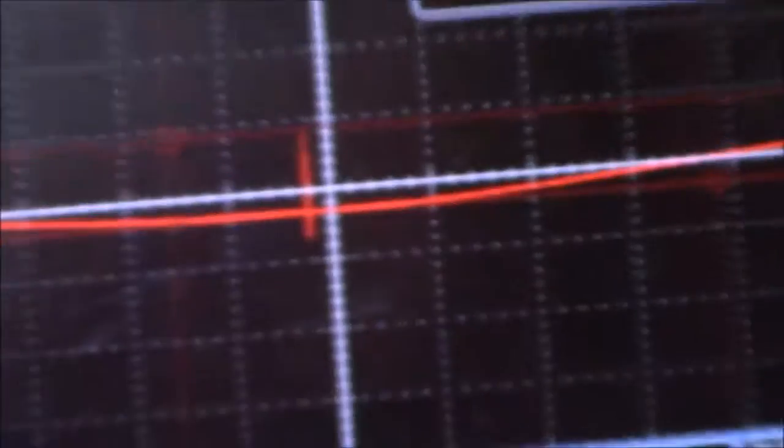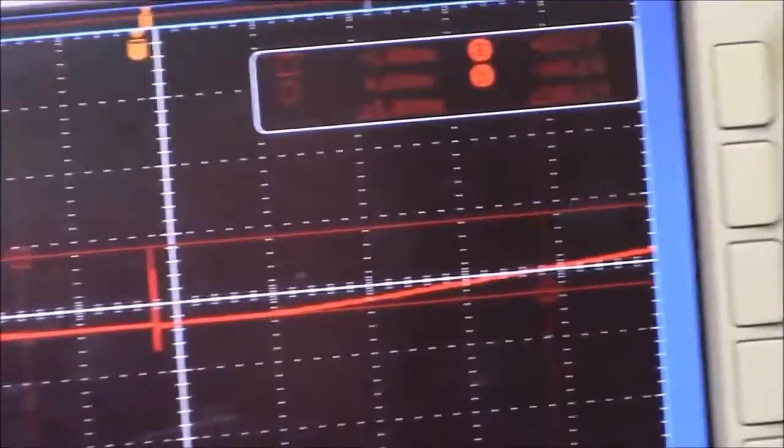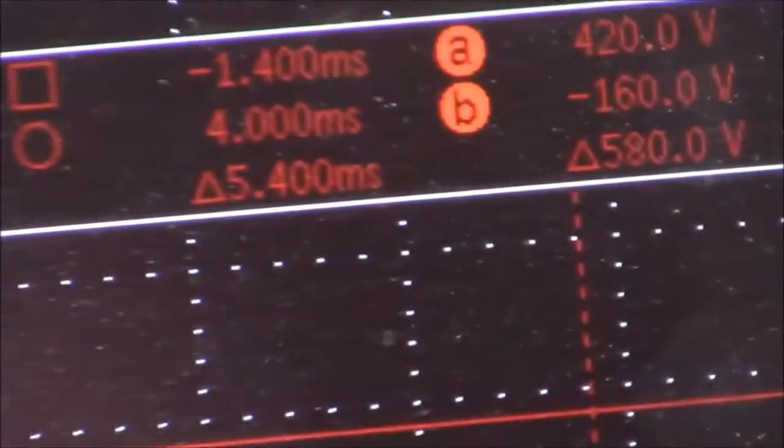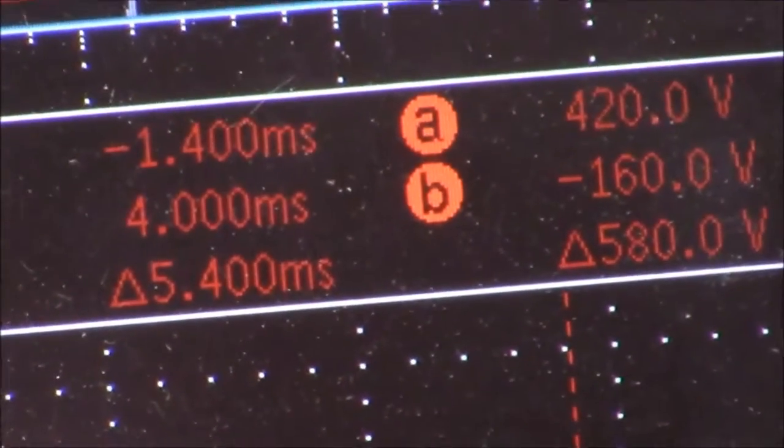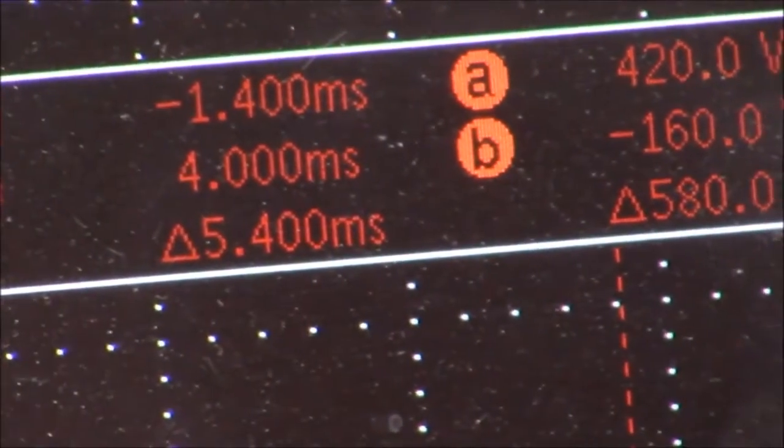And this one is almost identical to the previous one, we're at about 580 volts. So very similar type of technology with respect to attempting to clamp the ring wave transients.